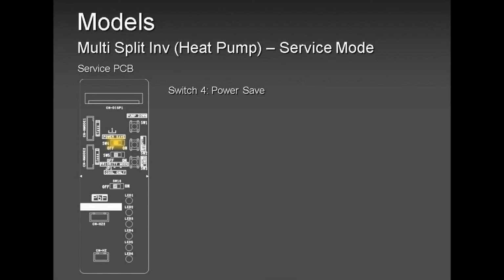Why? Because you're running that compressor to the maximum, and at that moment you will get all your pressures, the correct amount of gas in your system, as well as the correct running amps. That's the best way to use this function, test run.